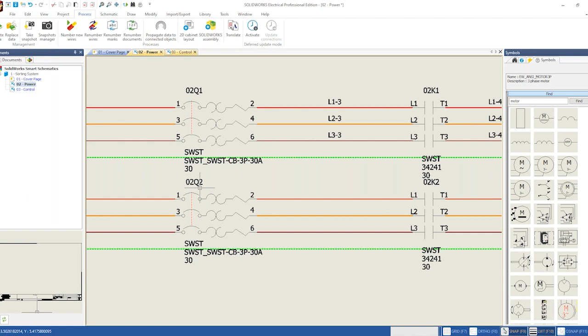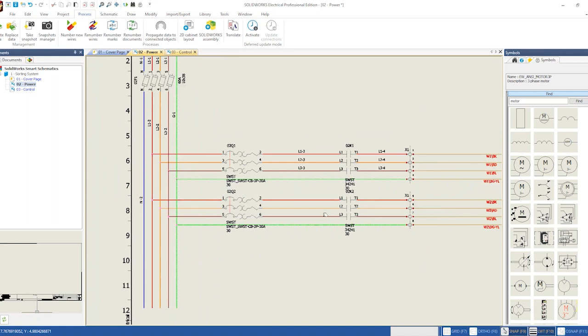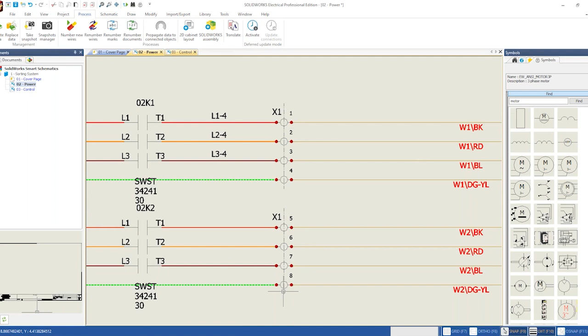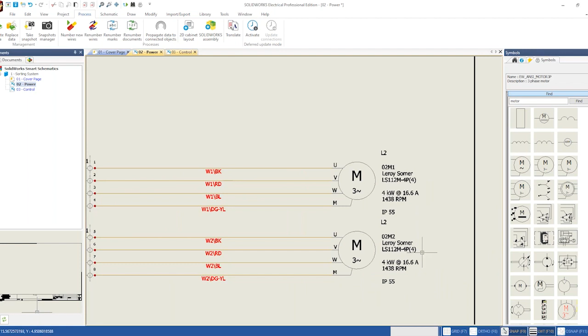By default, it automatically increments my tags: 02 Q2 is what that incremented to, and 02 K2 is what that incremented to. It kept my terminals within the same strip but created new terminal blocks, and automatically incremented the cable information and the motor information. So I can simply do a copy and paste — it works wonders for that.